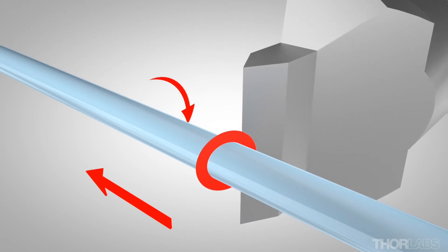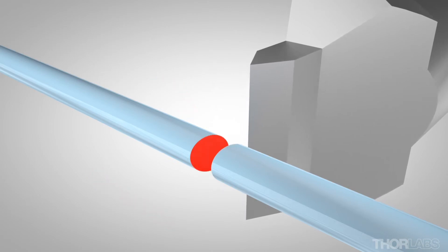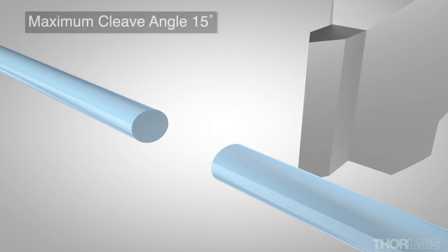When the blade strikes the fiber, the crack propagates across the cleave plane and results in an angled cleave.